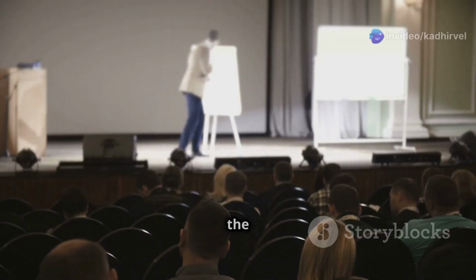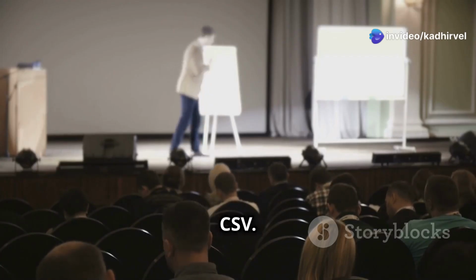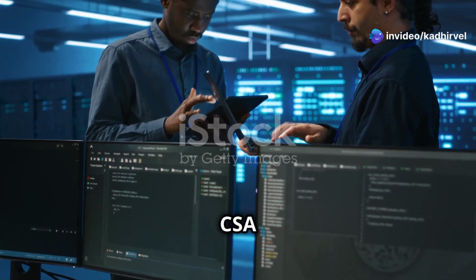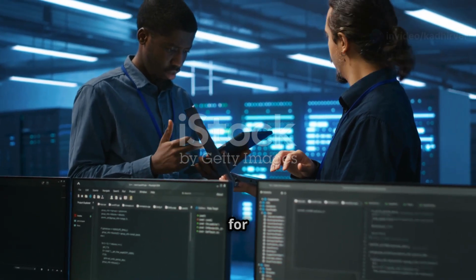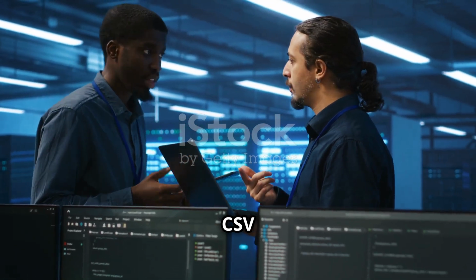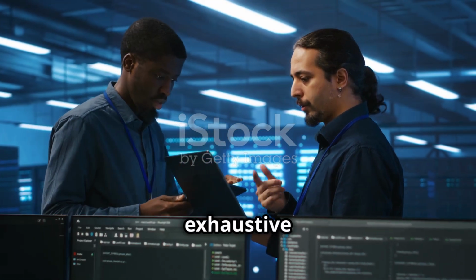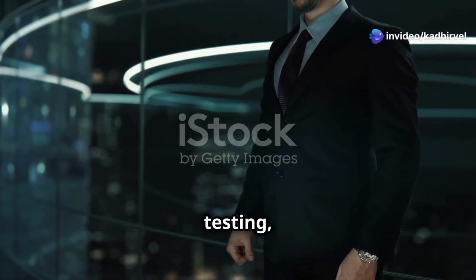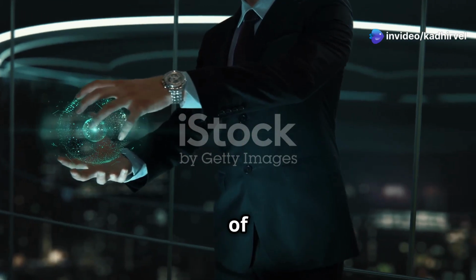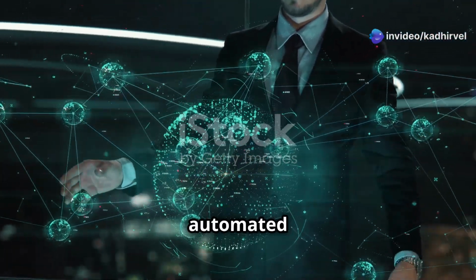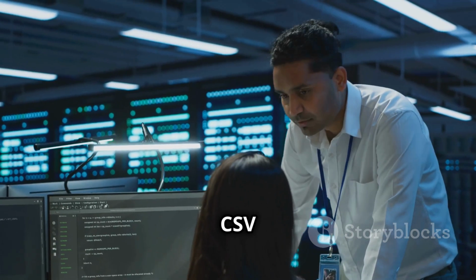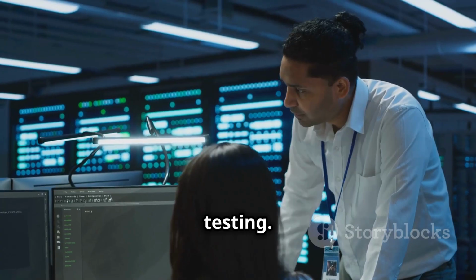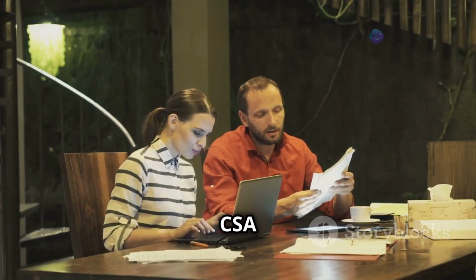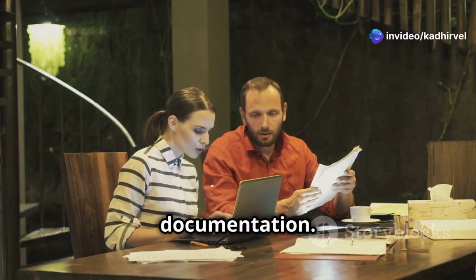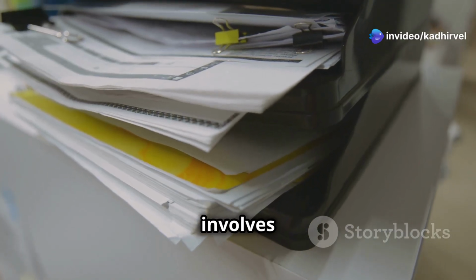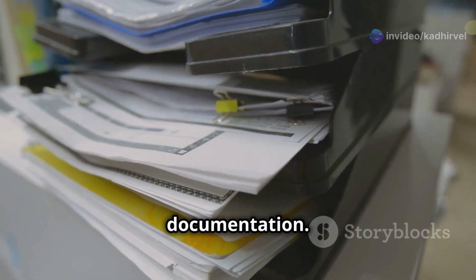Alright, let's dive into the key differences between CSA and CSV. When it comes to focus, CSA is all about risk-based testing for critical areas, whereas CSV aims for full system validation through exhaustive testing. In terms of testing, CSA utilizes a mix of scripted, unscripted, and automated methods. On the other hand, CSV primarily relies on scripted testing. When we look at documentation, CSA promotes fit-for-purpose and efficient documentation. CSV, however, involves extensive and rigid documentation.